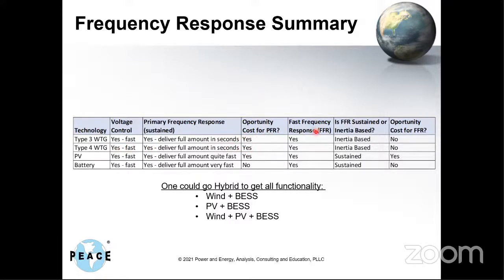Can they do fast frequency response? I didn't show the example, but we have field measurements of that as well, and the answer is yes. You can take some energy out of the rotating inertia of the wind turbine and inject that into the grid - an inertia-based fast frequency response. There are consequences and caveats to it, but it can be done.